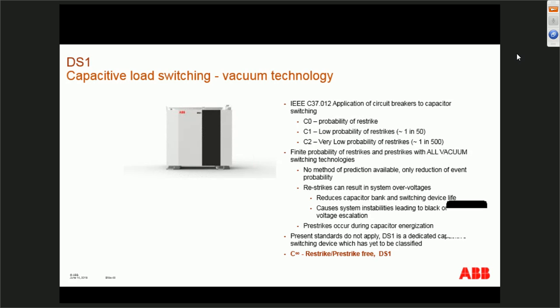It actually has dry air insulated poles. It uses a diode internal to the pole itself, a diode stack, and then it uses a mechanism which is perfectly timed that only allows the diodes to conduct for half a cycle, and then it's fully closed. Once it's fully closed, those diodes are bypassed, and it's just like having a straight piece of bus bar from your cap bank into your system. But it also does this at your zero crossings.